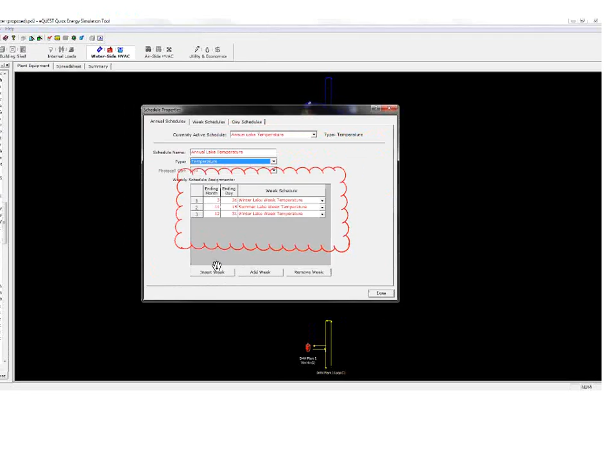So after I got the lake well representing my cooling tower and geothermal, I had to come up with a way to represent the fan energy of the cooling tower, since I don't have the cooling tower anymore, or it's not in the model. There's an auxiliary under the condenser water loop. I figured I could put in the power the motor is on, so the 5.6 kW is the motor size on the cooling tower.